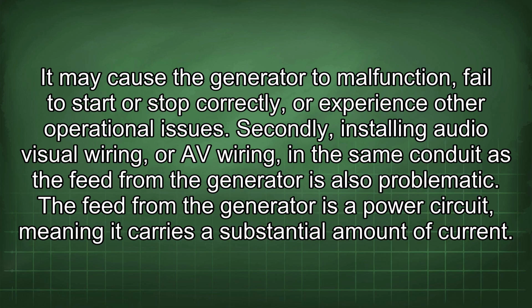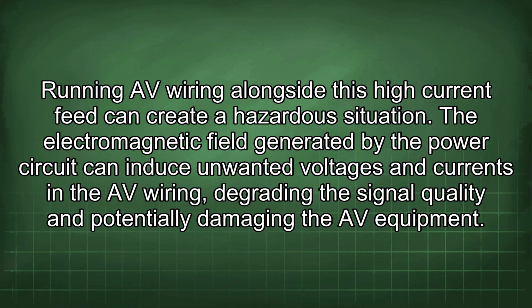Secondly, installing audio-visual wiring, or AV wiring, in the same conduit as the feed from the generator is also problematic. The feed from the generator is a power circuit, meaning it carries a substantial amount of current. Running AV wiring alongside this high current feed can create a hazardous situation. The electromagnetic field generated by the power circuit can induce unwanted voltages and currents in the AV wiring, degrading the signal quality and potentially damaging the AV equipment.